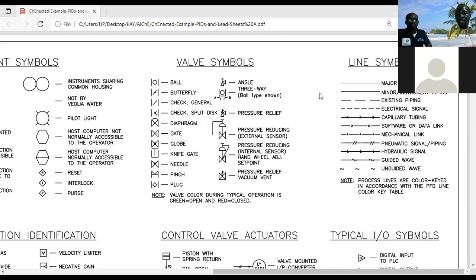Your PSV will just open. One is designed to open suddenly, with a pop sound, to relieve the excess pressure at once and come back to the normal operating pressure of that vessel or line. The other one will open gradually to relieve the excess pressure. So that is the major difference we use as a yardstick between the pressure relief valve and the pressure safety valve.